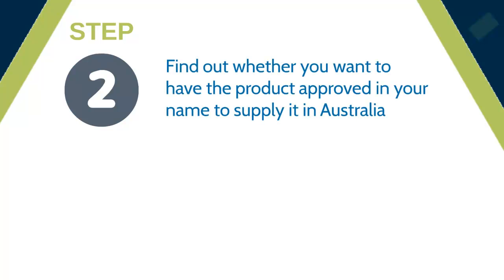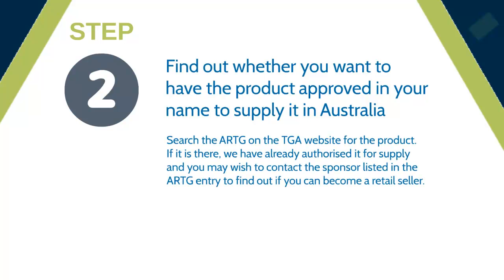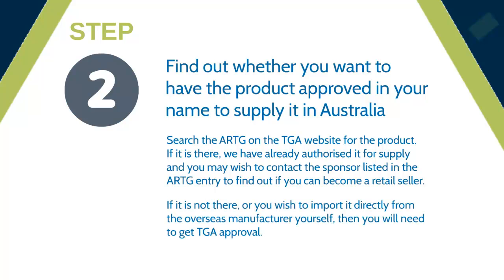Step 2. Find out whether you want to have the product approved in your name to supply in Australia. Search the ARTG on the TGA website for the product. If it is there, we have already authorised it for supply, and you may wish to contact the sponsor listed in the ARTG entry to find out if you can become a retail seller. If it is not there, or you wish to import it directly from the overseas manufacturer yourself, then you will need to get TGA approval. The overview contains a link to the ARTG.